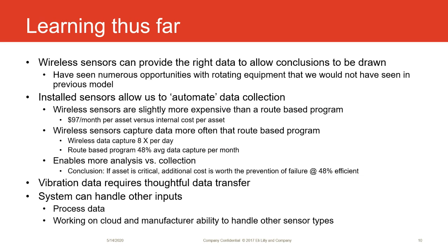You also have to look at how your failure modes generate. So if you don't feel, from a criticality standpoint of that equipment, that the failure mode will generate before the next monthly reading - let's say for vibration - then by all means go with your route-based functionality. But if that asset is critical enough - let's say it's a bottleneck operation, it's one of one, a standby piece of equipment that has to run, like a generator - you're in Puerto Rico, you've got a standby generator, and when there's a hurricane that thing has to run when it's turned on - that's a scenario where you'd probably want to do something like this.